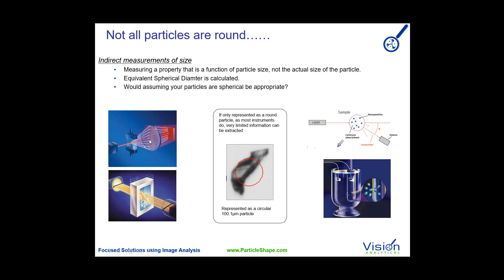In the case of laser diffraction, for example, we're hitting particles with light and then measuring the angle of the diffracted light that comes off. We use that to make a calculation and assume the particles are spherical to give you a particle size. Sedimentation is also a very common technique used for particle sizing of calcium carbonate — we're looking at the measurement of the sedimentation rate and making an assumption with mathematical calculations that particle size is related to sedimentation.